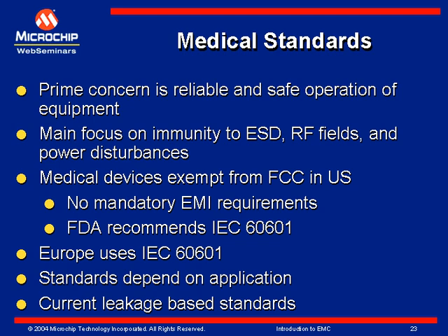In the US, the FDA, Food and Drug Administration, controls the medical standards, but they do not create any medical standards. Most of the time they refer to the IEC 60601 standard. In Europe, IEC 60601 is almost mandatory. Again, the standard depends on the application. Each medical equipment may need to meet different requirements.